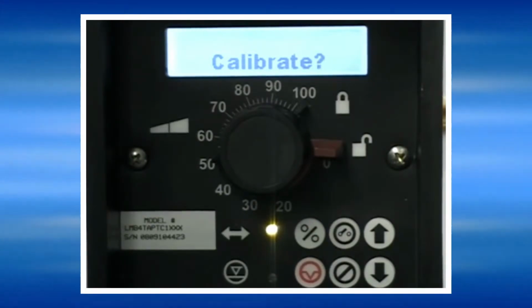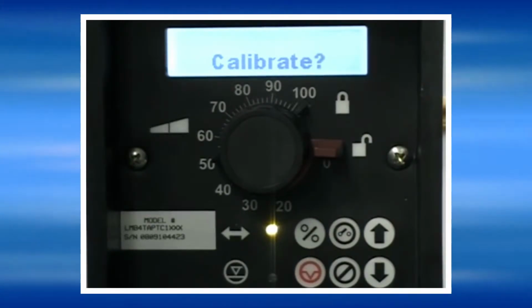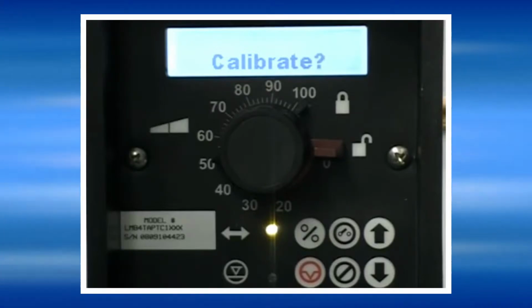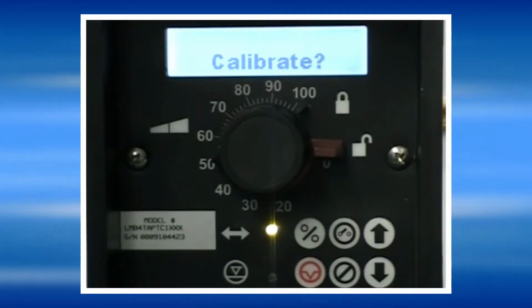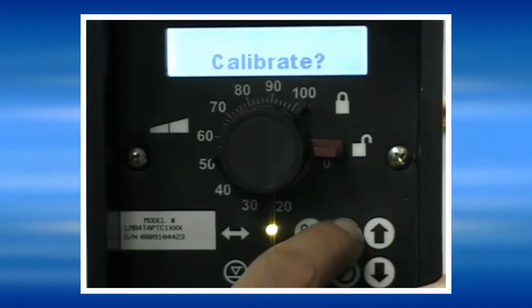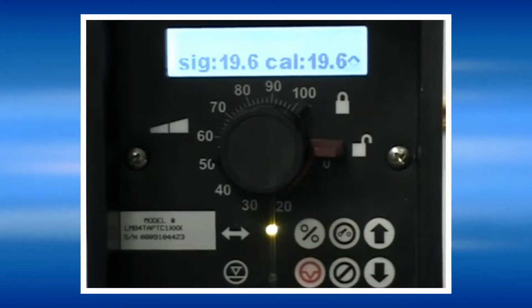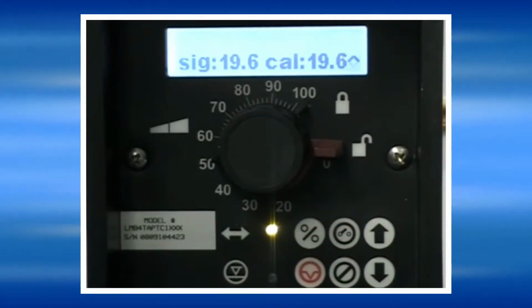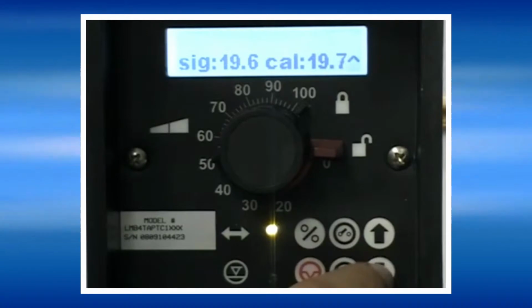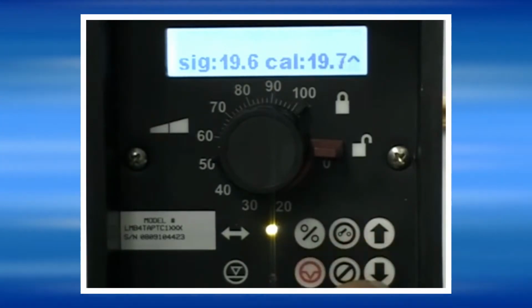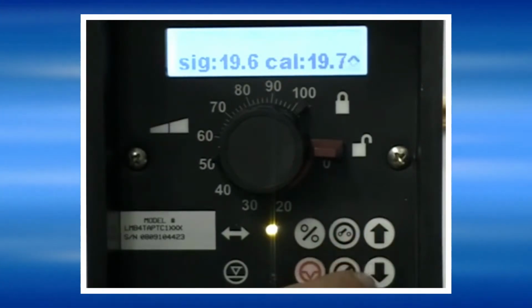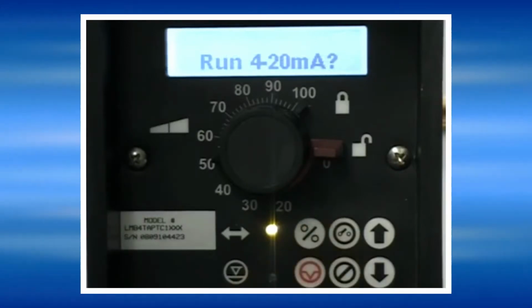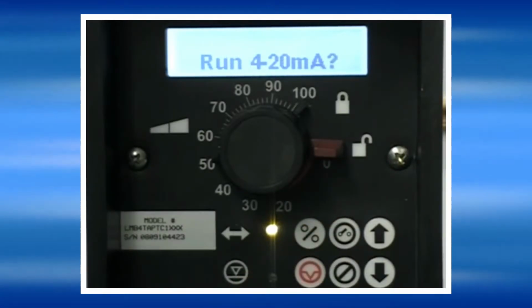If you know what the milliamp signal is that's coming from the device that's controlling the pump, you can actually calibrate the pump to match the milliamp input signal. If we press Yes, it'll tell us what the signal is that's being received and what we want the calibration value to be. Once the calibration is set, simply press the Yes key. Then the pump will prompt us to run in the 4 to 20 milliamp mode.